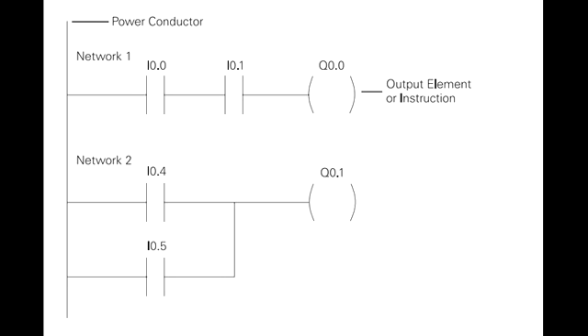Rungs are sometimes referred to as networks. A network may have several control elements, but only one output coil. In the example program shown, I0.0, I0.1 and Q0.0 represent the first instruction combination. If inputs I0.0 and I0.1 are energized, output relay Q0.0 energizes. The inputs could be switches, push buttons, or contact closures.